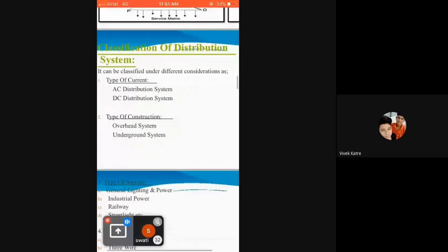So for this, we have to consider the conductor's current carrying capacity during design of that feeder. Now let's move towards the distributor. So what is distributor? Distributor is also a conductor, but with tapping. It is having tapping. We have already discussed the basic construction of feeder, distributor and service mains in yesterday's lecture. The current through a distributor is not constant because tappings are taken at various places to supply the power to consumers.